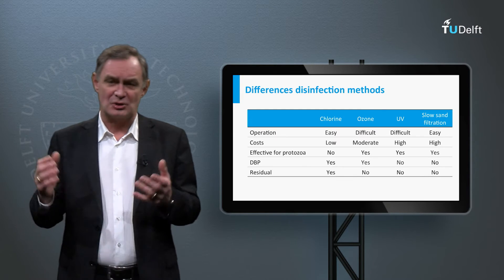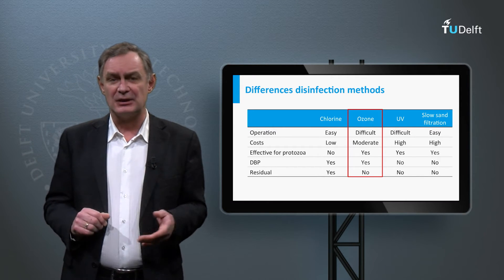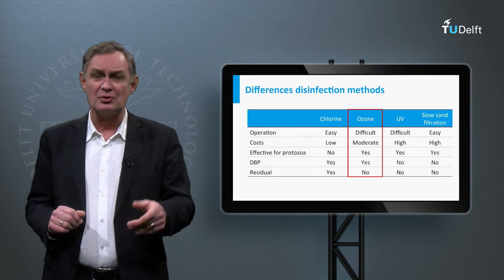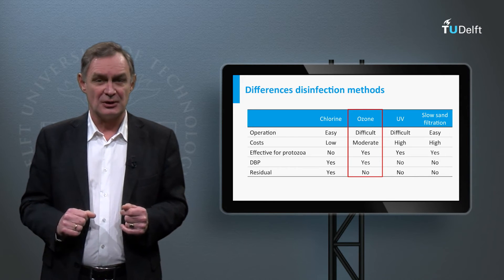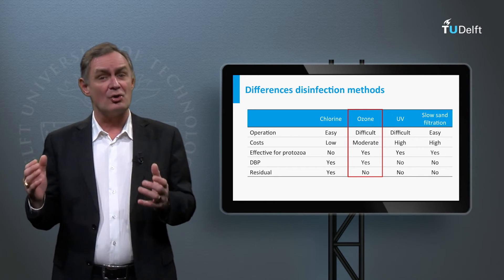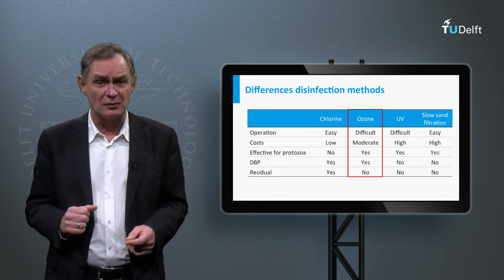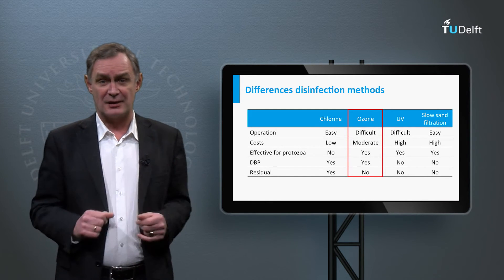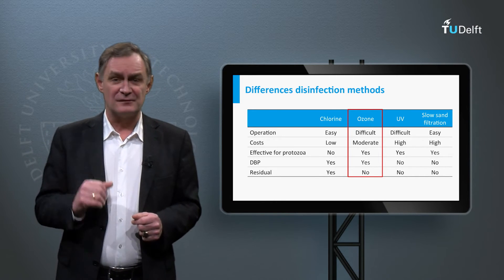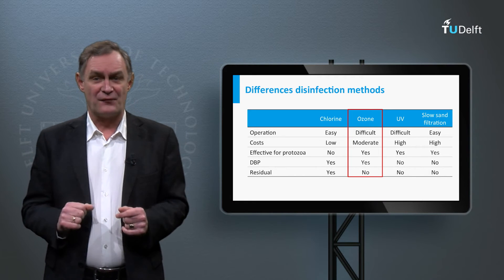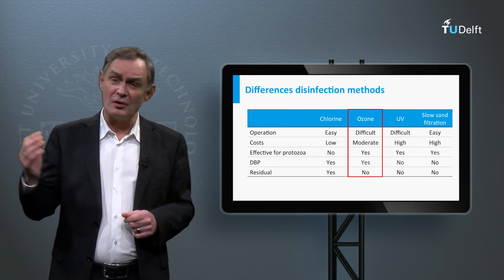Ozone is generated from oxygen present in air or in pure oxygen gas. Due to its instability, ozone should be generated in situ and requires a high level of maintenance and operational skills. The initial investment costs for equipment are also relatively high. Ozone is more effective than chlorine for inactivation of protozoa and short contact times are required. However, when bromide is present in the water, the disinfection by-product bromate is formed, and ozone doesn't maintain a residual level in the distribution system.